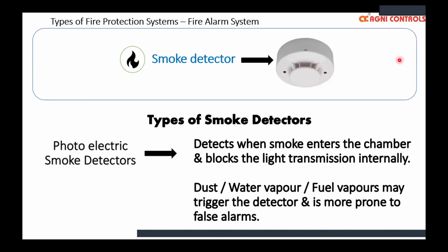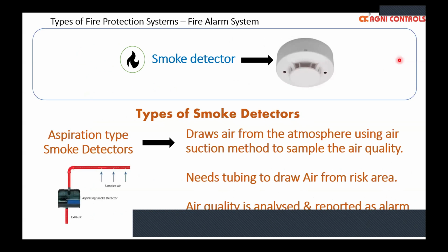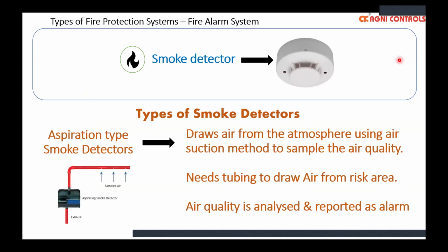There are different types of smoke detectors. The most commonly used are the photoelectric smoke detectors, and aspirating type smoke detectors, where air is drawn through tubing and the air quality is sampled, and based on the air quality it confirms if it's smoke or not.